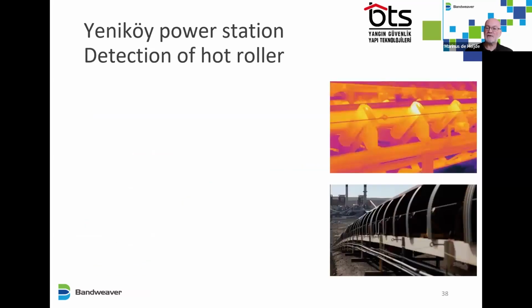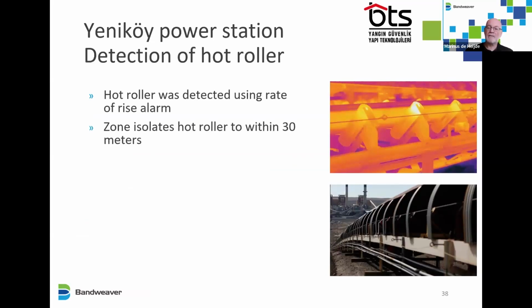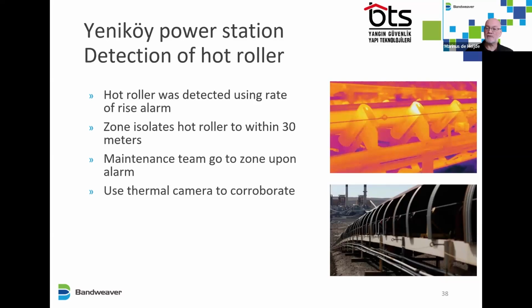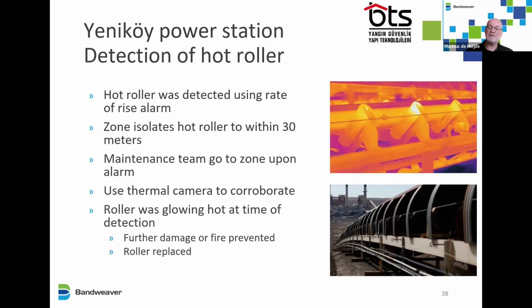So what happened? Within a fairly short amount of time, they had a detection of a hot roller. They used the rate of rise alarm for that. So it was not at the 57 to 61 degrees, but it was the rate of rise alarm, which is 5 to 7 degrees increase within a minute. So this isolated the incident to within 30 meters. That's how we installed the zoning. A maintenance team went then to the particular zone with a thermal camera to inspect that zone, and they found the roller pretty quickly, and it was glowing hot. So instead of a fire, they just replaced the roller and prevented potentially a huge issue there, because if you got coal on fire on a conveyor belt, the fire could have spread over 20 kilometers basically.